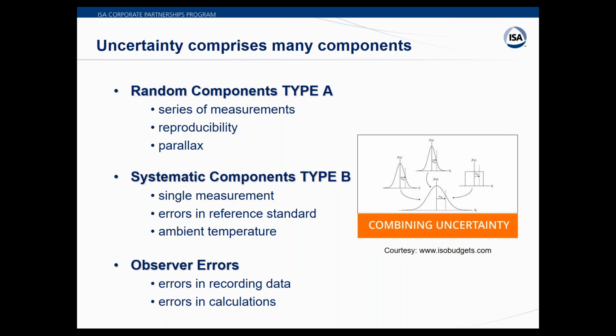Things that are random: if you're making multiple measurements, so let's say you do Roy's up-down test two or three times, each test point that he data logs going up on pressure is going to be slightly different. He's using the same method, the same pump, and the same procedure, but the numbers aren't going to be exactly the same out to 3-4 decimals. Obviously, it's not going to be reproducible. Parallax is really your eye looking at an analog gauge, and everybody's eyes are a little different. Depending on the angle of your head, you get parallax. So those are examples of random things. There are plenty of other examples.